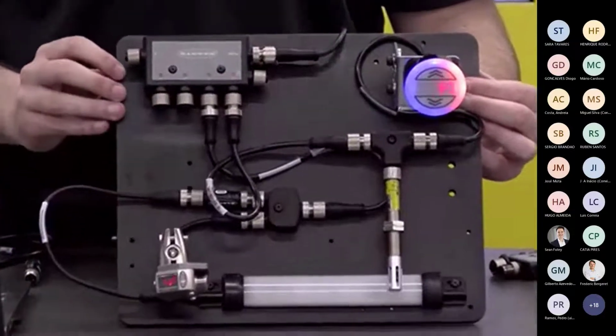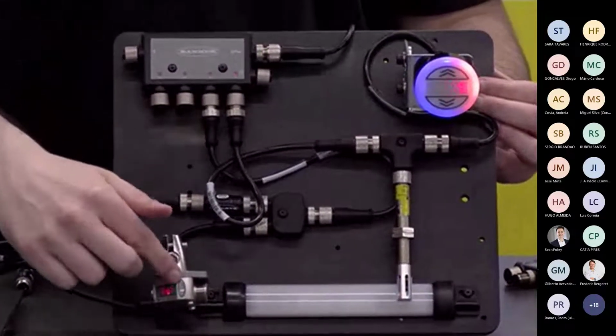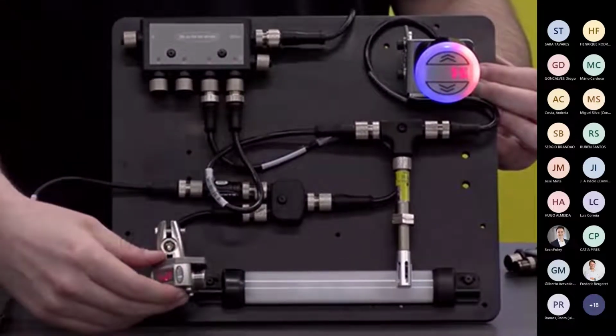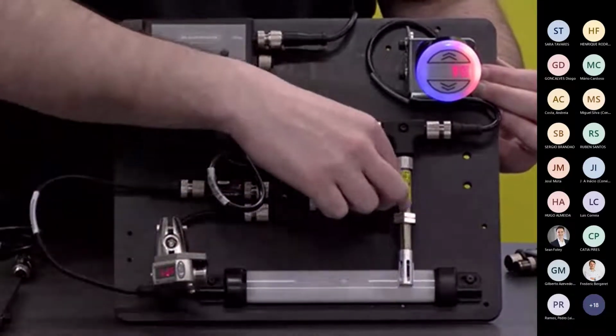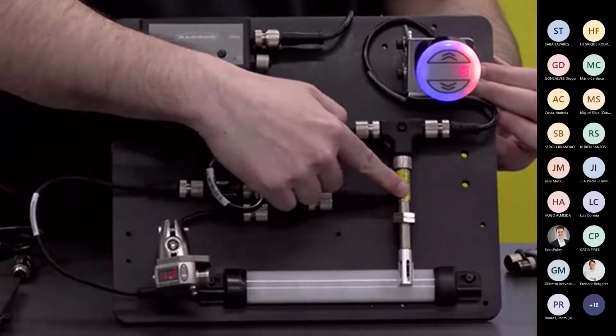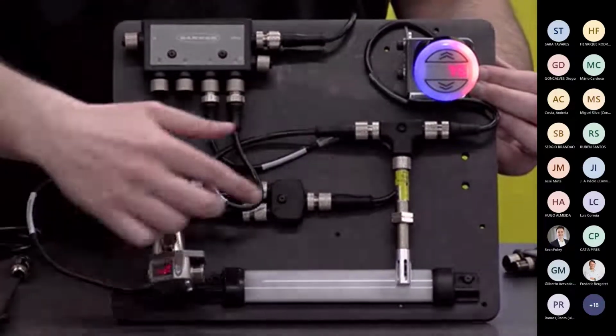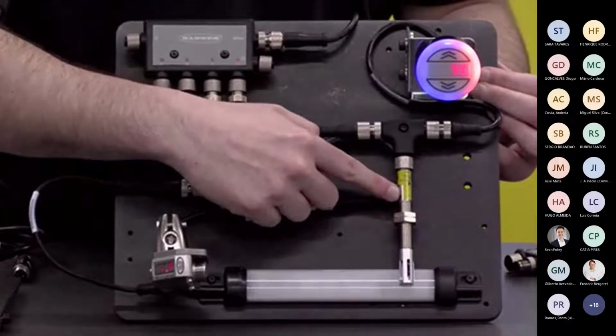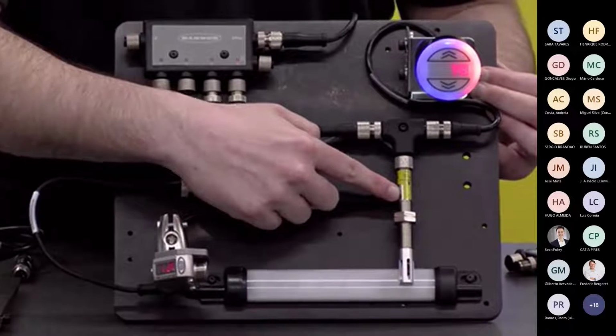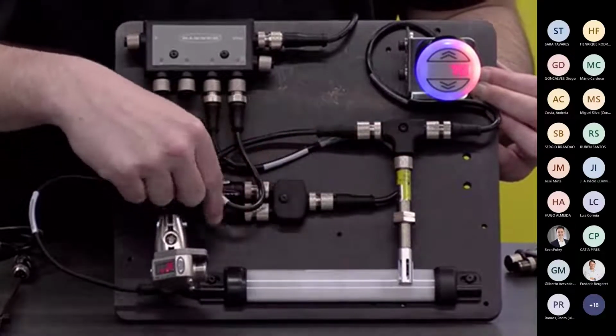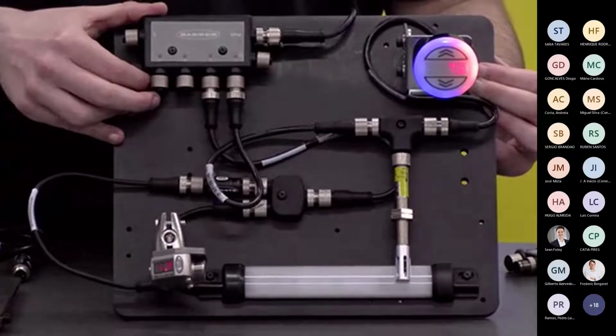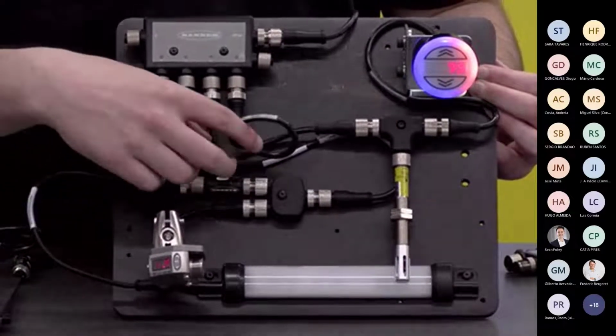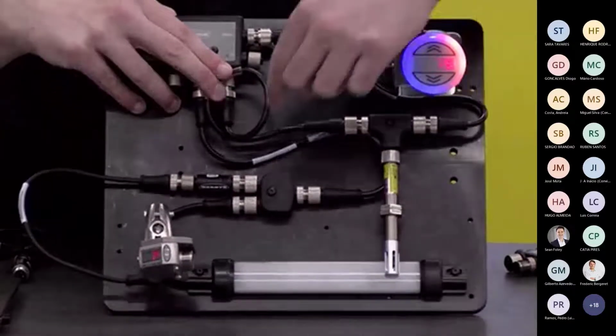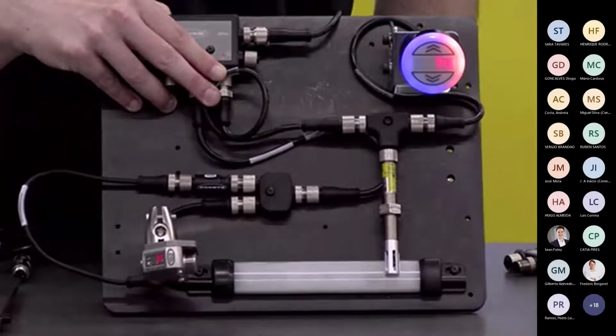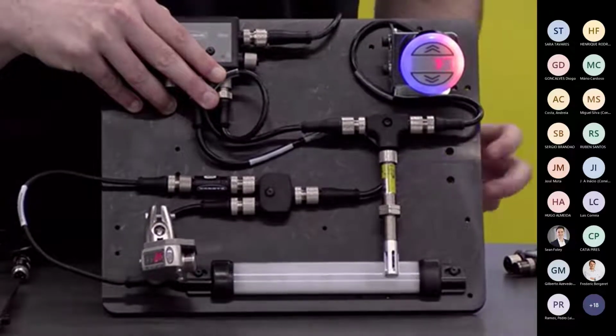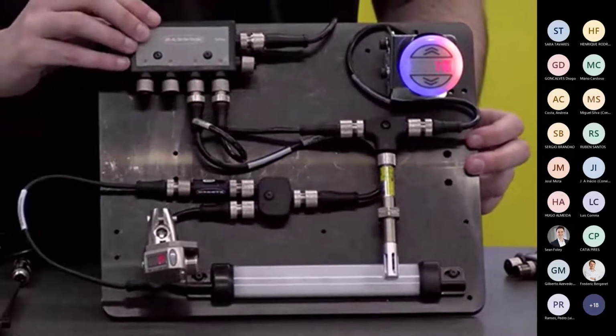Maybe you have an analog sensor monitoring a tank level and want to harvest that sensor signal data. Here, maybe you're monitoring the temperature and humidity of an environment with a 4 to 20 milliamp signal sensor. We're teeing into those sensors and sending the data back to our DXM R90 Industrial Controller - converting it over to a unified serial protocol with this compact converter, about the size of an AA battery, and sending that data into the DXM R90.